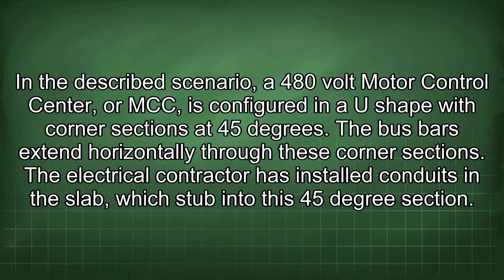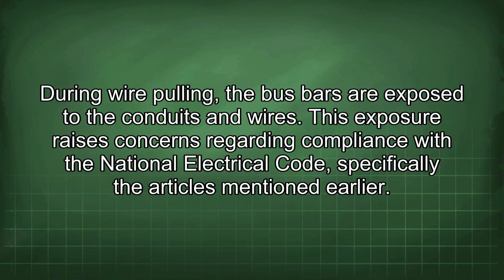In the described scenario, a 480-volt motor control center, or MCC, is configured in a U-shape with corner sections at 45 degrees. The bus bars extend horizontally through these corner sections. The electrical contractor has installed conduits in the slab, which stub into this 45-degree section. During wire pulling, the bus bars are exposed to the conduits and wires. This exposure raises concerns regarding compliance with the National Electrical Code, specifically the articles mentioned earlier.